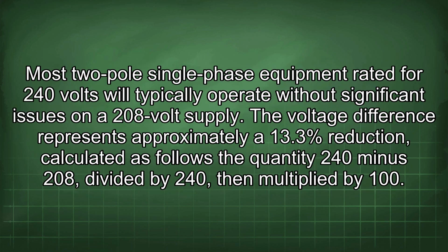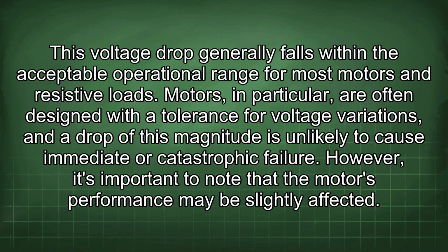Most two-pole single-phase equipment rated for 240 volts will typically operate without significant issues on a 208-volt supply. The voltage difference represents approximately a 13.3% reduction, calculated as follows: the quantity 240 minus 208 divided by 240, then multiplied by 100. This voltage drop generally falls within the acceptable operational range for most motors and resistive loads. Motors, in particular, are often designed with a tolerance for voltage variations, and a drop of this magnitude is unlikely to cause immediate or catastrophic failure.